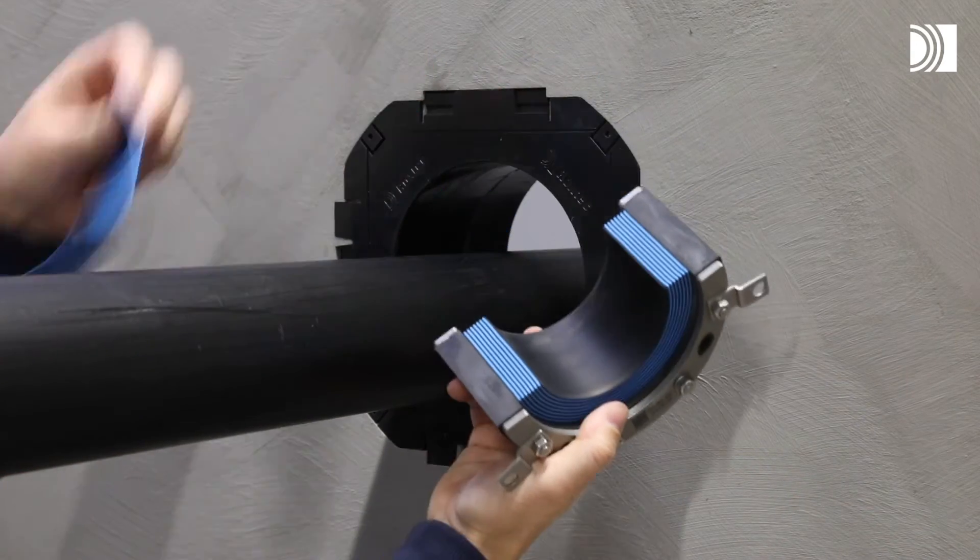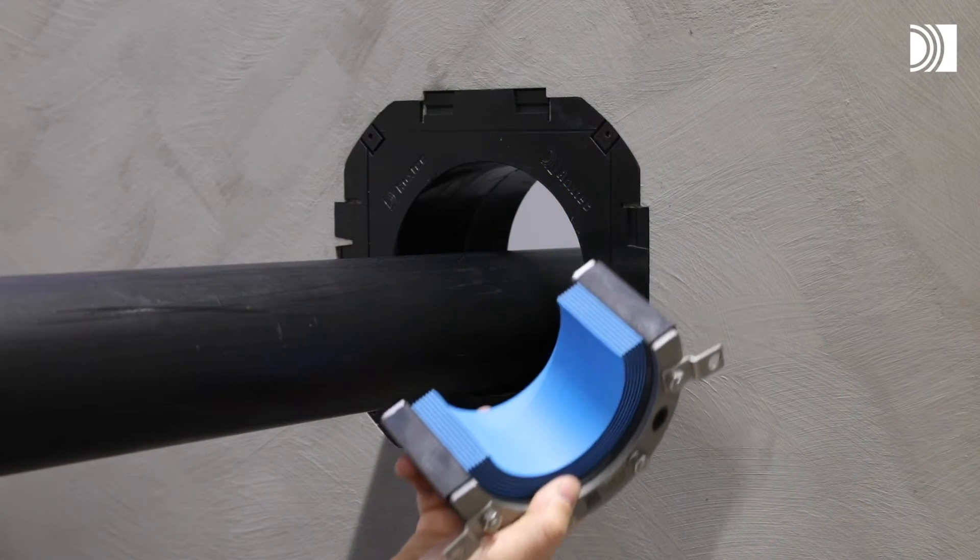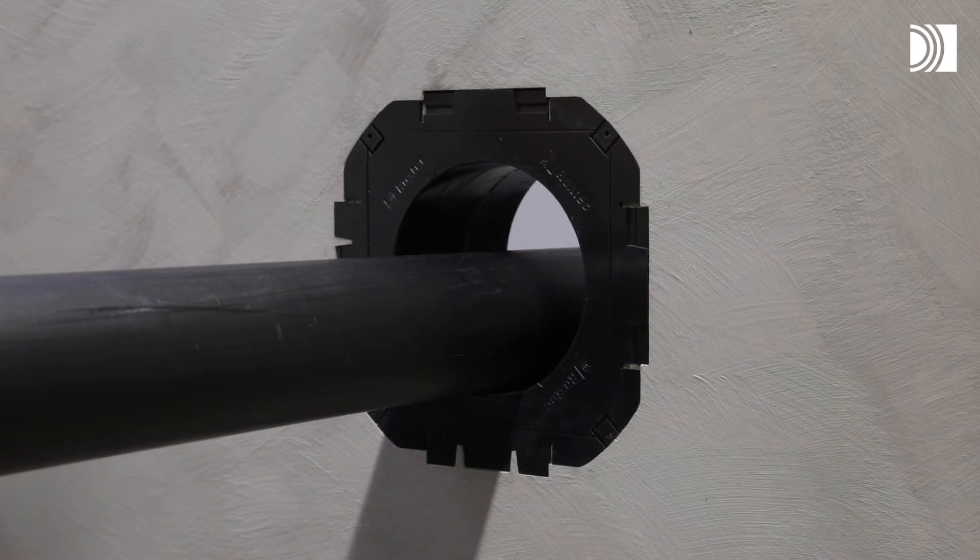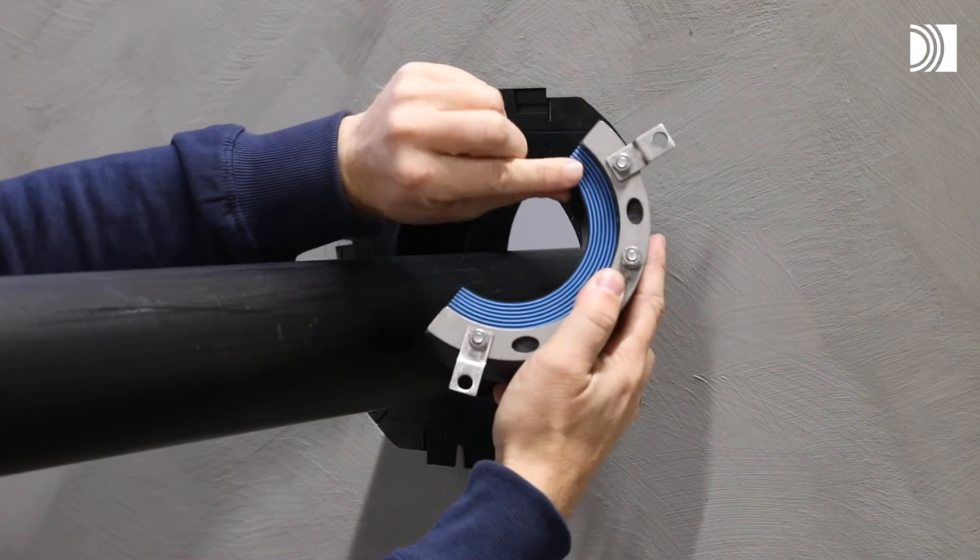Adapt the seal by peeling off layers. The number of layers may not differ by more than one between the corresponding seal halves. Do not remove the last layer.